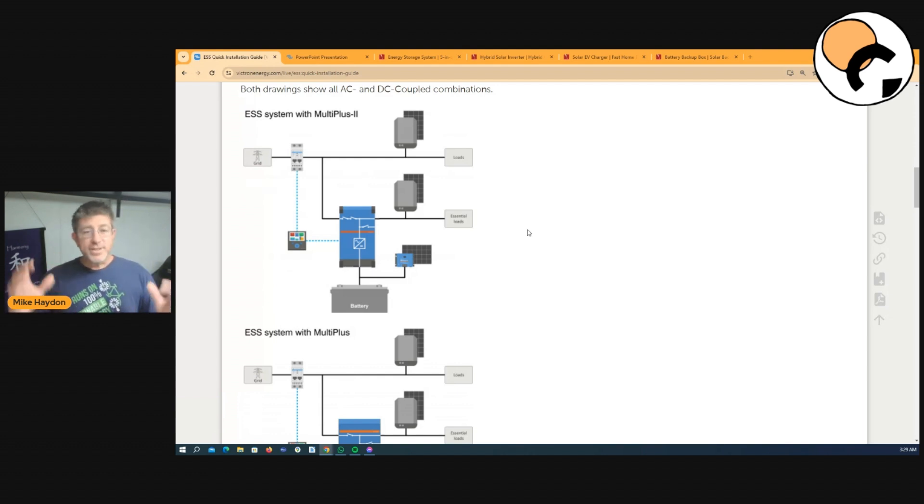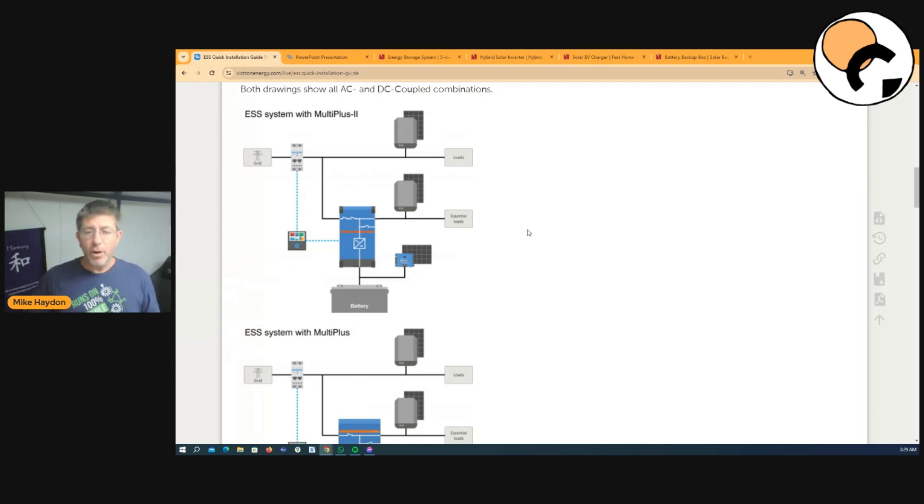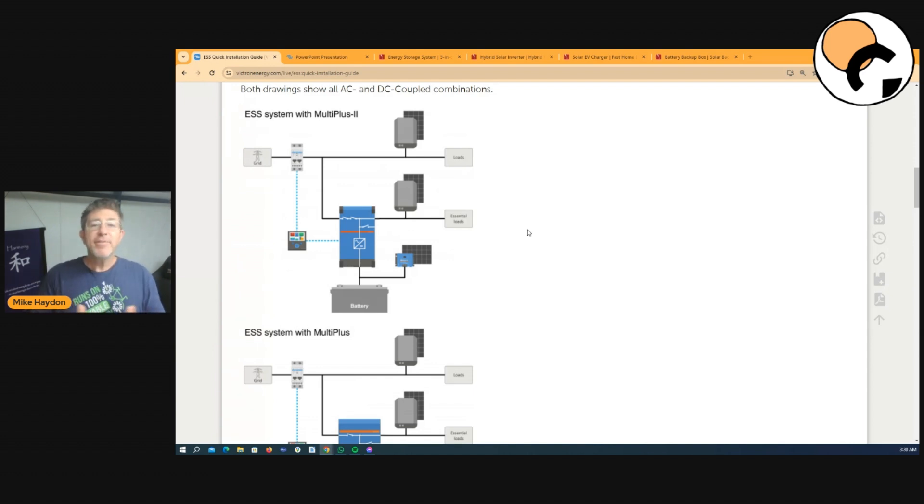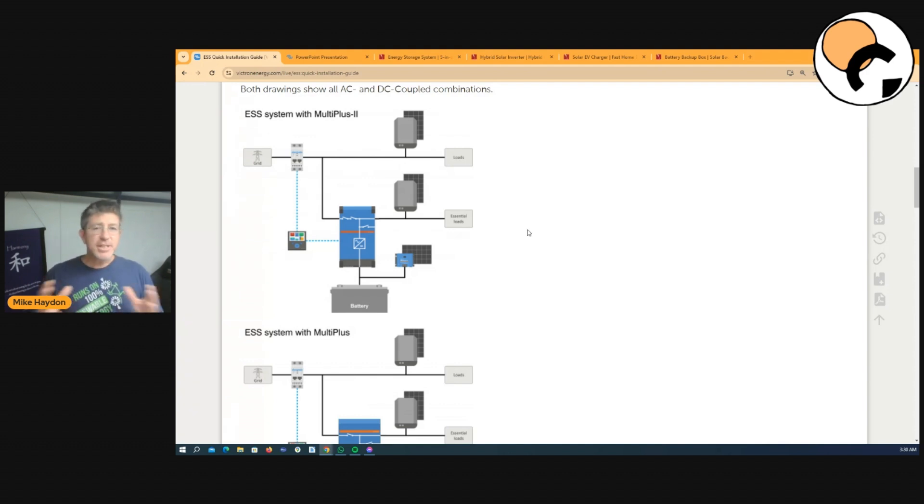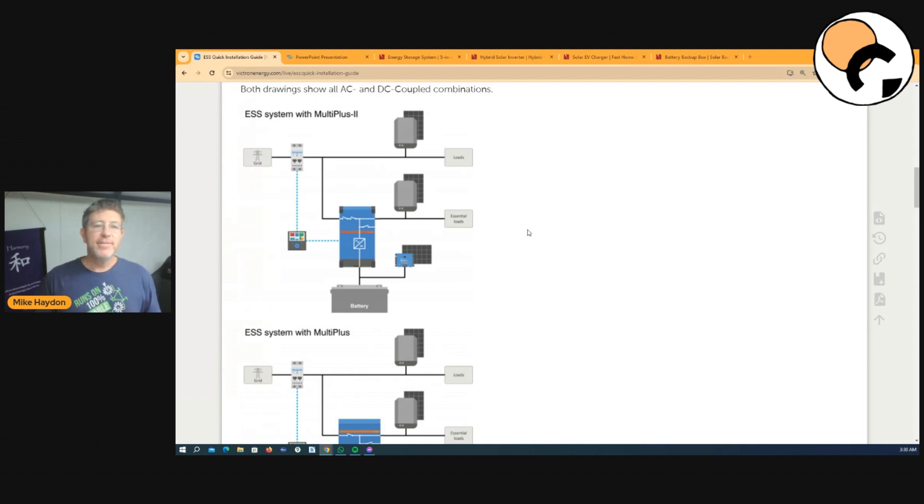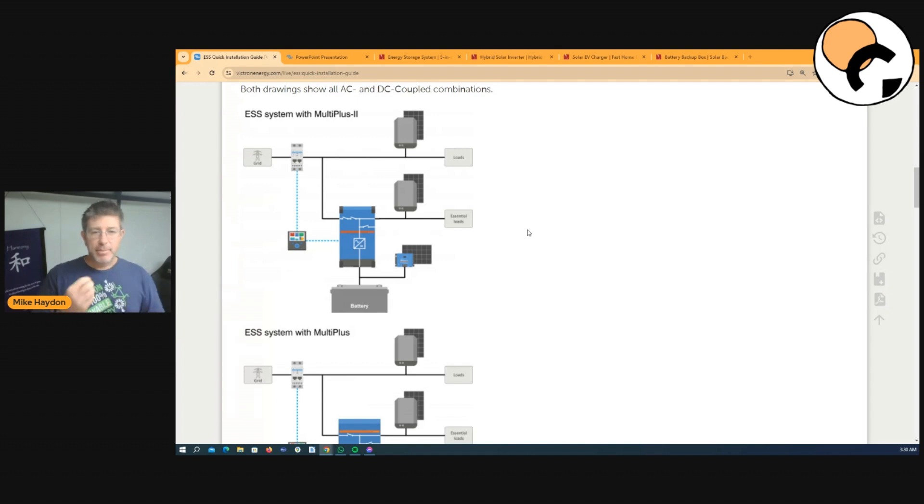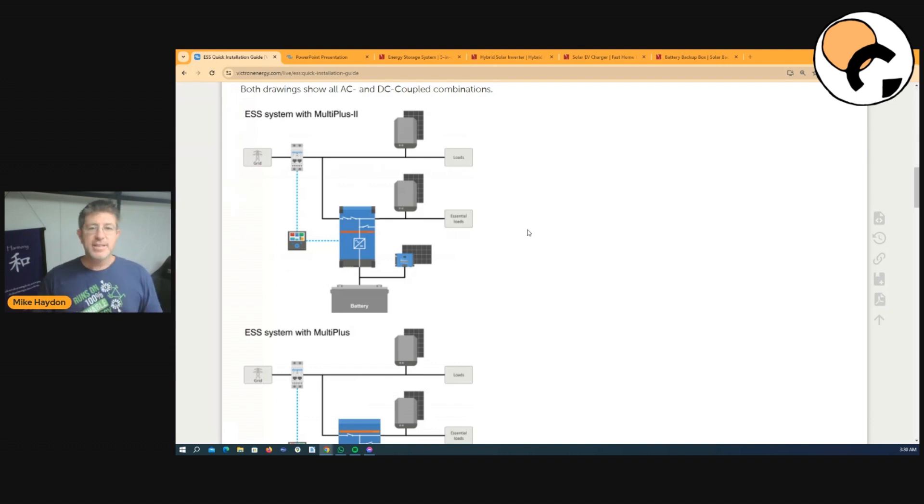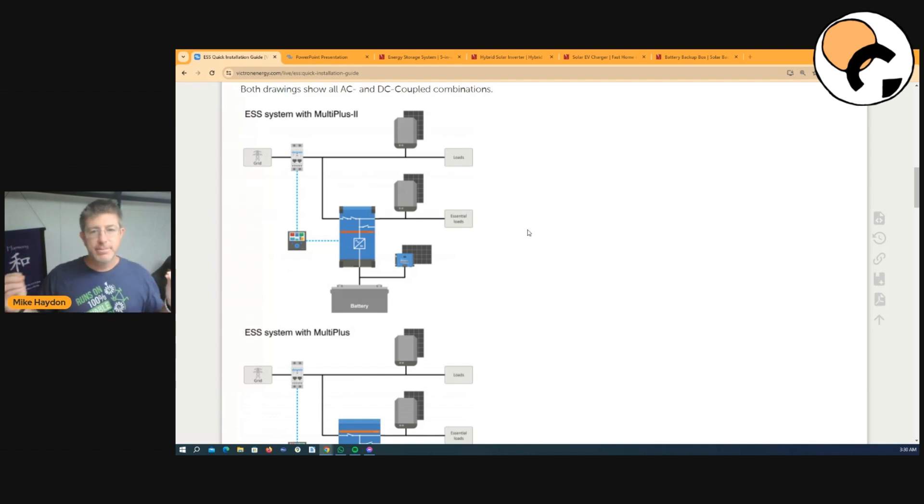What's happened more and more over the years, we've seen a lot more three-phase systems and systems get bigger and bigger. One of the things that's held back with Victron and a lot of the other off-grid products, Selectronics is the same, is the limitation per phase. If you have a three-phase house and you want three-phase loads and you put an inverter on each single phase, the problem that happens, you're limited to the size that inverter per phase. So just as an example, if you get a five KVA inverter on each phase, from a single phase point of view, you can only use five KVA per phase. So if you have the kettle or jug, toaster, your boiling water on one phase, and then you turn the air conditioner on that one phase, you're going to have a blackout. So it's really important that traditionally in a Victron three-phase system, your phases have to be really well balanced.